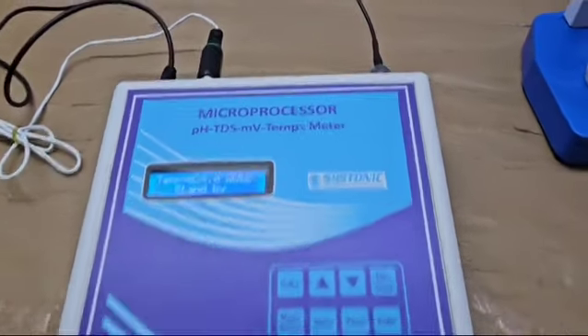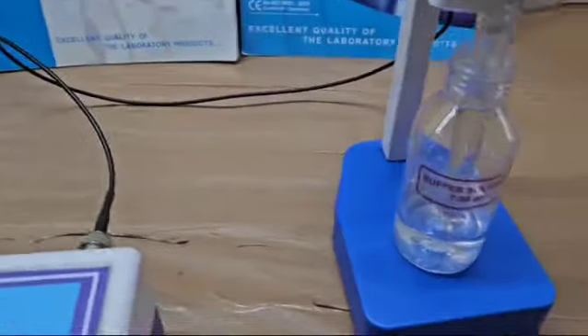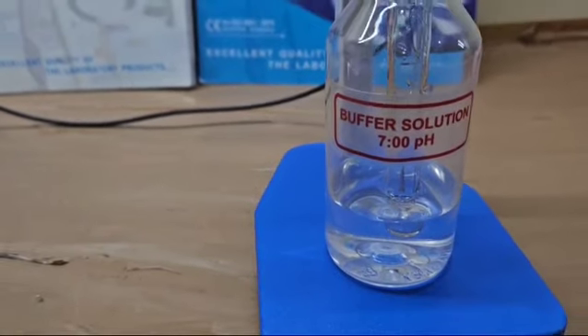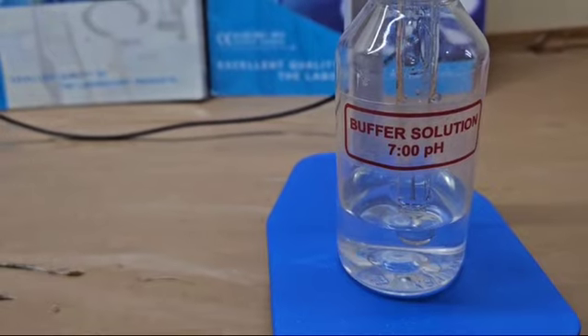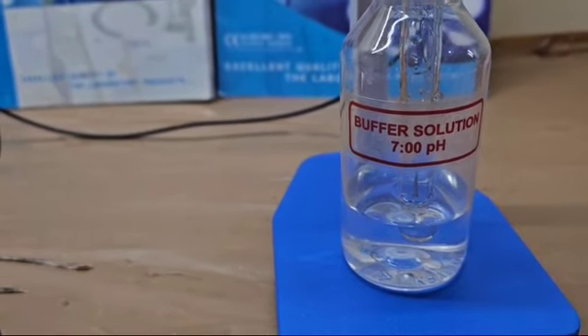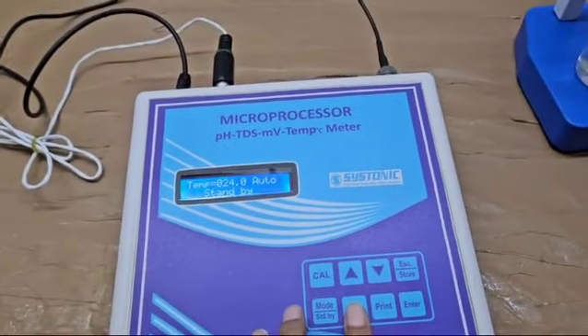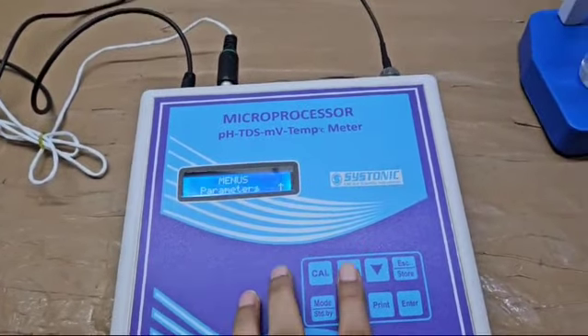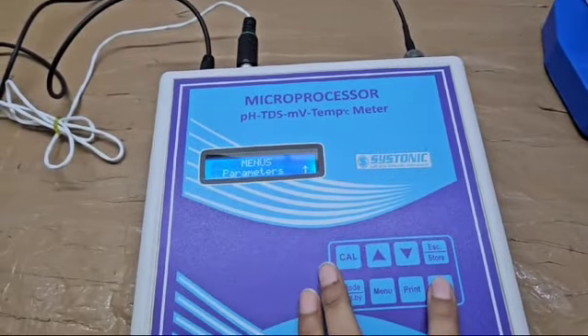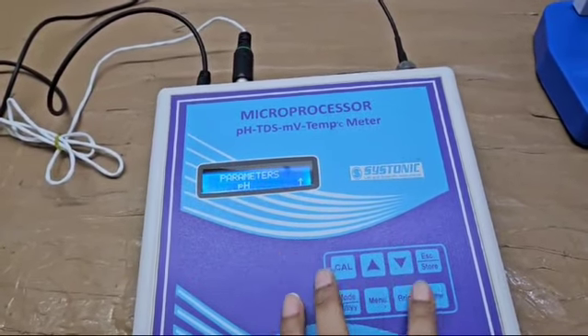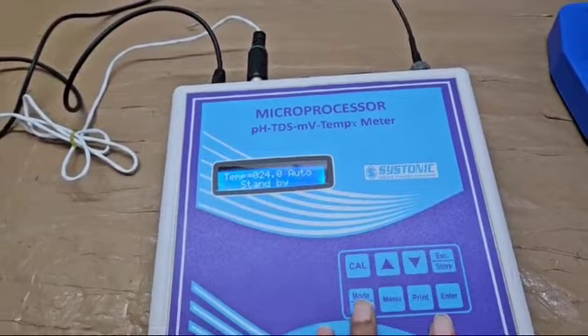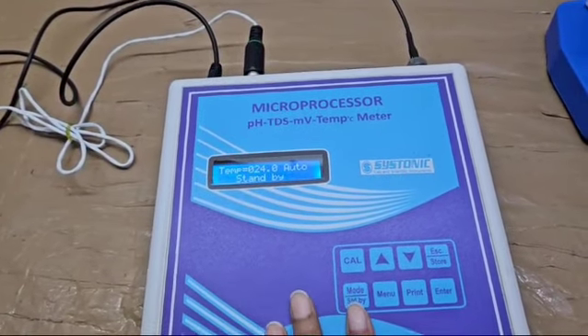Now for the pH, as I have connected the electrode and dipped it in the 7 pH buffer solution, which you can prepare by the instructions provided in the manual. So now you can also go to menu, and from here you can change the parameters. Press enter, and to pH press enter. So now your parameter is changed.